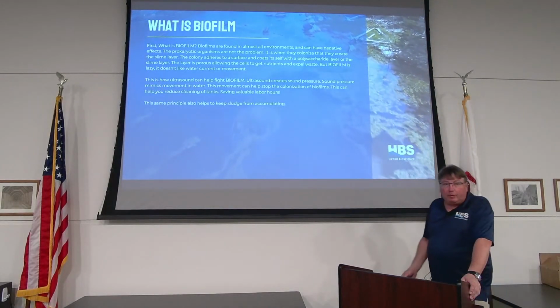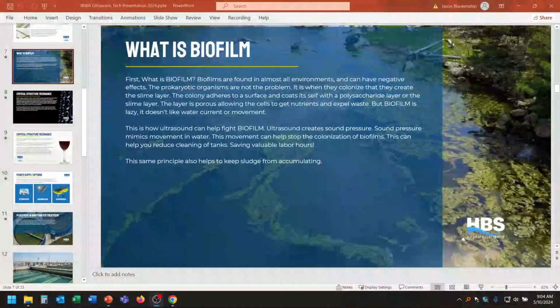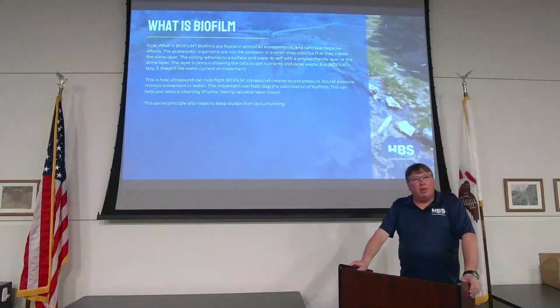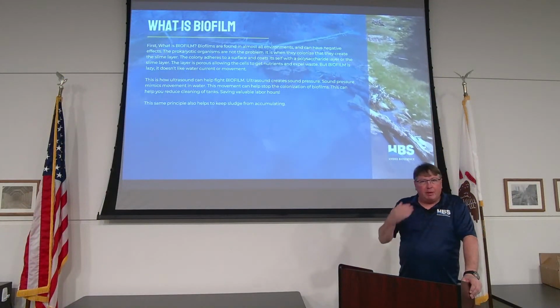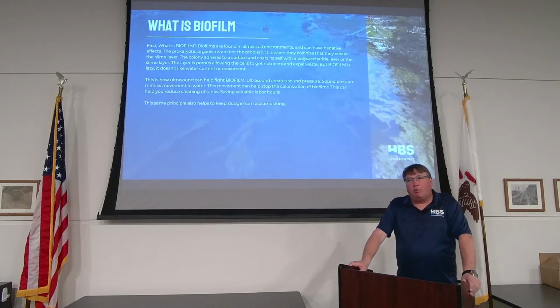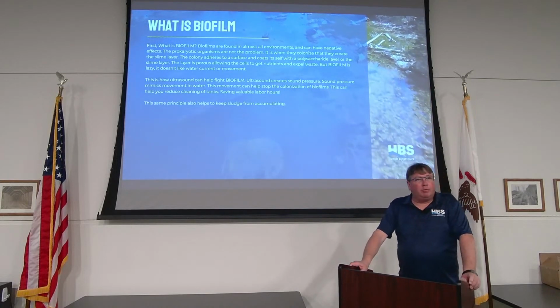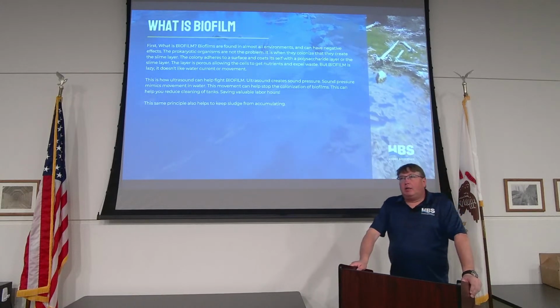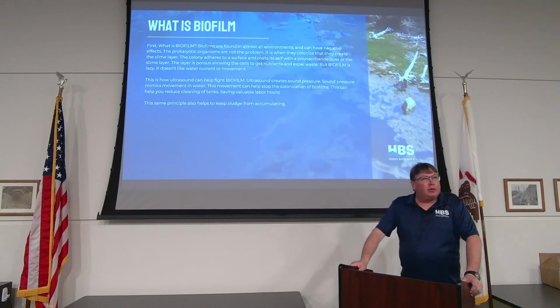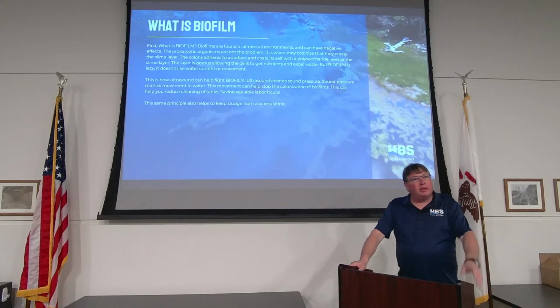What is biofilm? Biofilm is in every body of water. It's just not a problem until it starts to colonize. And that's when you get that film surface built up on everything, the slimy stuff. What we use is sound pressure. The way these systems work is they're emitting ultrasounds, and it's mimicking sound pressure. So it's mimicking movement. So the biofilms do not want to colonize. They do not want to stay in one place. It's just like biofilms on a rock in a river. They're always on the backside where it's calmer, and it always builds up there.